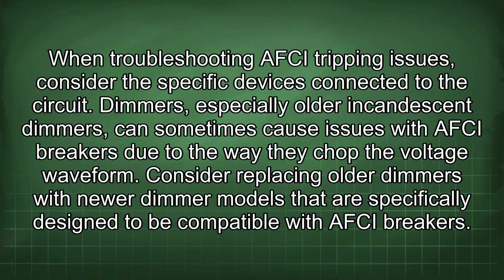When troubleshooting AFCI tripping issues, consider the specific devices connected to the circuit. Dimmers, especially older incandescent dimmers, can sometimes cause issues with AFCI breakers due to the way they chop the voltage waveform. Consider replacing older dimmers with newer dimmer models that are specifically designed to be compatible with AFCI breakers.